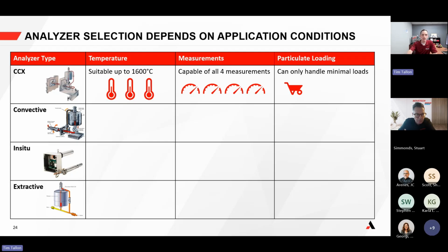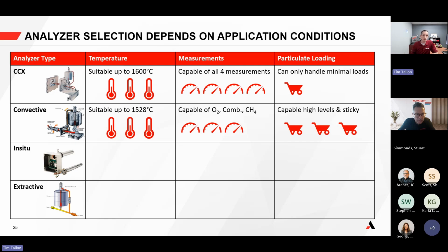Now I want to contrast that with the convective type. It's also suitable for much higher temperatures, up to 1528 degrees Celsius. But the challenge is that, due to the speed within the convective type, there's no flow sensor, but we are capable of the added measurements of excess oxygen, combustibles, and methane. Those 3 measurements can be built in. So at high temperature, 3 measurements, and also the proven capability for high levels of particulate and even sticky particulate, even saturated streams we've seen as well.